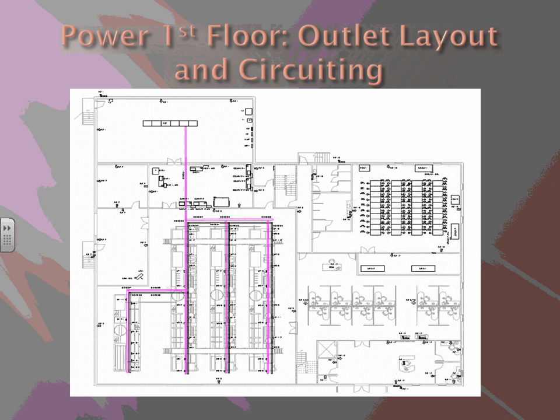This is just the first floor. I'll just tell you right now, there are 2 UPSs right here, and PDUs will be right here and here. What Derek pretty much talked about: we took 40 racks in here, and we took 5,000 per rack, and multiplied that by 1.25 continuous load, and we got our KVA. With the UPSs, if they're on for 15 minutes, then the generator will kick in and those will run. And UPSs are battery powered.